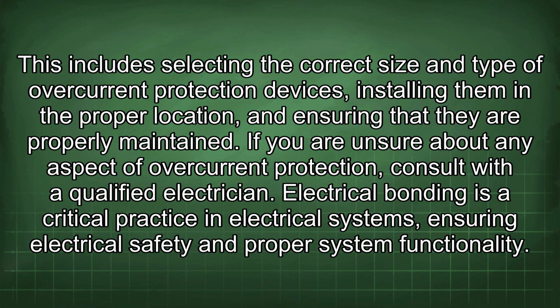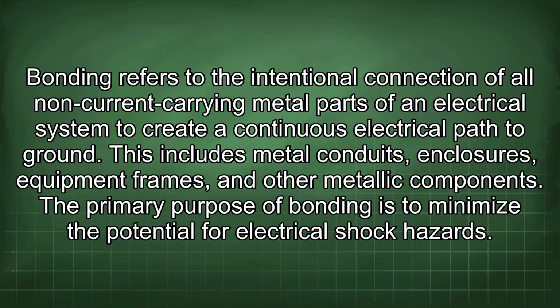Electrical bonding is a critical practice in electrical systems, ensuring electrical safety and proper system functionality. Bonding refers to the intentional connection of all non-current carrying metal parts of an electrical system to create a continuous electrical path to ground. This includes metal conduits, enclosures, equipment frames, and other metallic components. The primary purpose of bonding is to minimize the potential for electrical shock hazards.